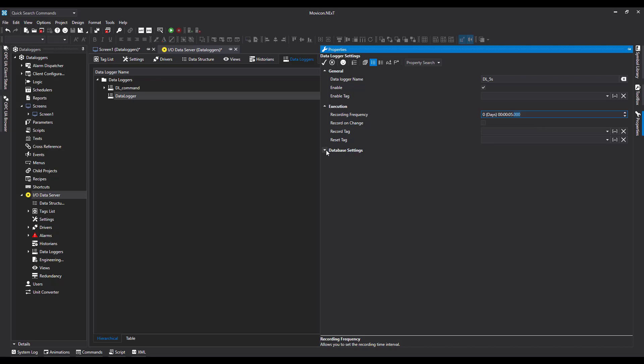Let's come down to Database Settings. We've got the Maximum Age of the database - how long do you need your data retained for. This can vary from industry to industry, and this is something you'll have to find out for legislation requirements. I'm going to set this to 720 days for our example, which is two years worth of data.